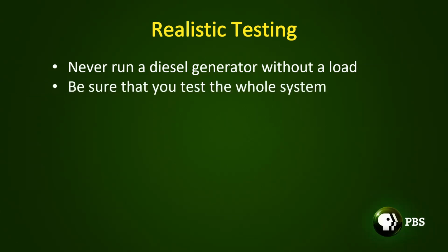Which kind of brings me to my second point. An emergency generator system is a system. There's a whole lot more to it than just that generator. You've got transfer switches, you've got other devices that have to act properly to make sure that that generator is doing what you want it to do. So when you test a system, test the whole thing. What do I mean? Pull the main breaker and let her fly. Make sure that the whole thing works.